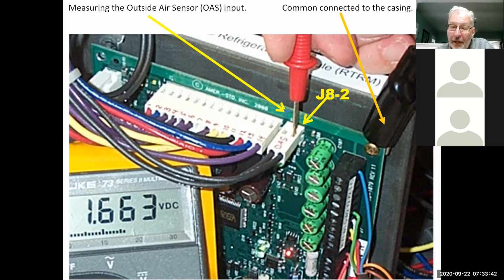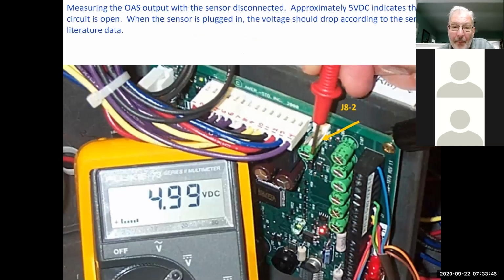So that's how you can test your outdoor sensor to make sure that it's reading the proper numbers. Now, if you were to take that sensor off here, pull the wire off, you should read 5 volts DC or 4.9, 4.99. And if you have the 5 volts DC here, that means the board is good. If you plug it in and it goes to 0, that means you got a shorted sensor. So there's good information just by taking some voltage readings here.